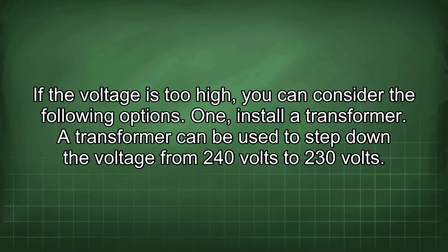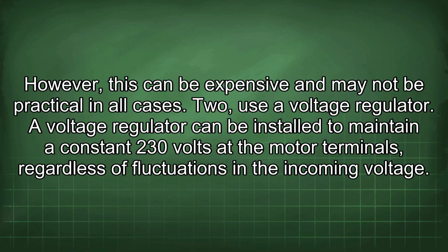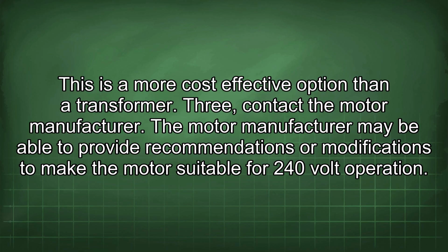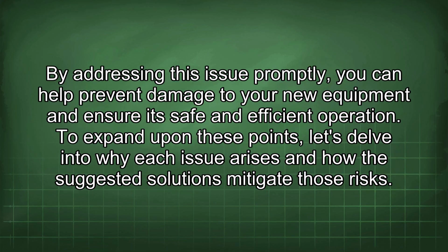If the voltage is too high, you can consider the following options. 1. Install a transformer. A transformer can be used to step down the voltage from 240 volts to 230 volts. However, this can be expensive and may not be practical in all cases. 2. Use a voltage regulator. A voltage regulator can be installed to maintain a constant 230 volts at the motor terminals, regardless of fluctuations in the incoming voltage. This is a more cost-effective option than a transformer. 3. Contact the motor manufacturer. The motor manufacturer may be able to provide recommendations or modifications to make the motor suitable for 240 volt operation.